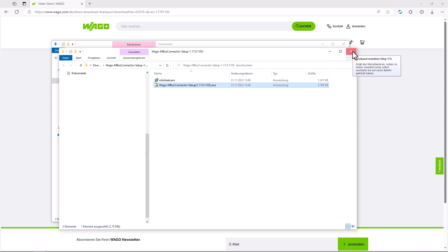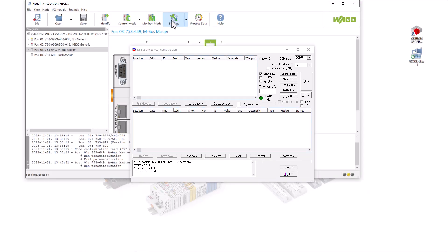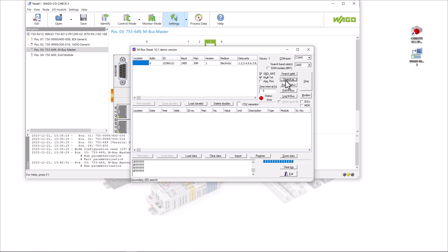We do not need the desktop icons as we usually open MB sheet via I-O check. If we now select the MBUS module in the I-O check and click on settings, MB sheet opens. There are two ways to search for meters, one via the primary address and one via the device ID. Since we have not assigned any primary addresses yet, it is likely that the meter connected to the MBUS still has the primary address assigned by the manufacturer, usually address 0 or 1. Therefore we start the search for the device IDs here, since they are unique. The connected meter is displayed.